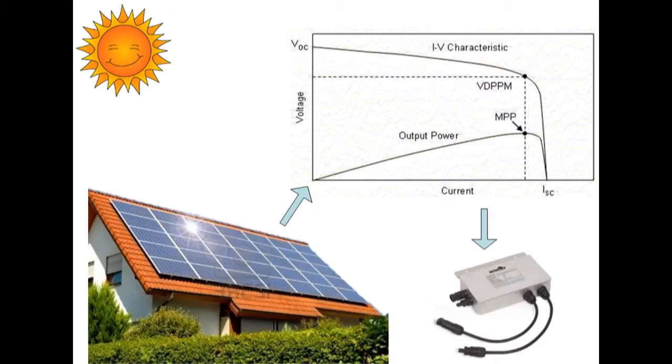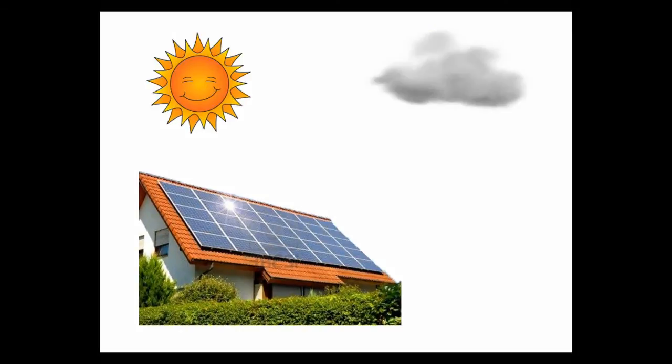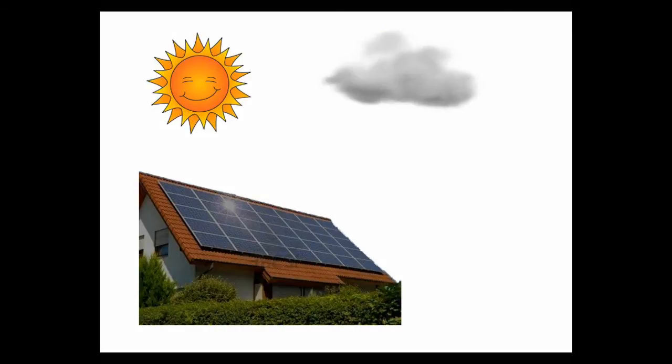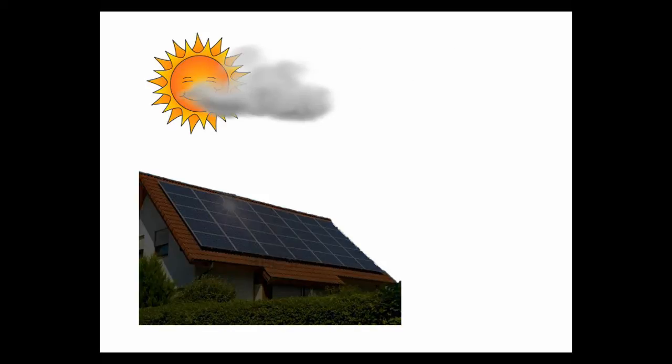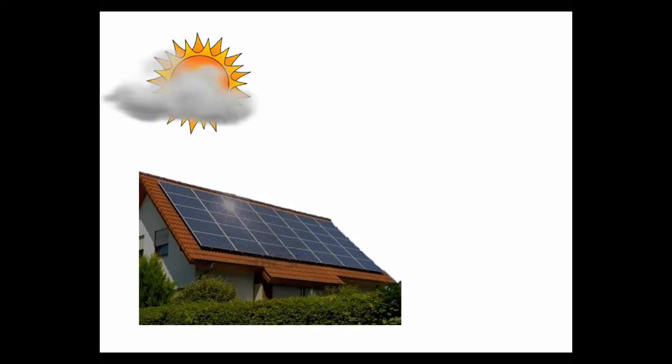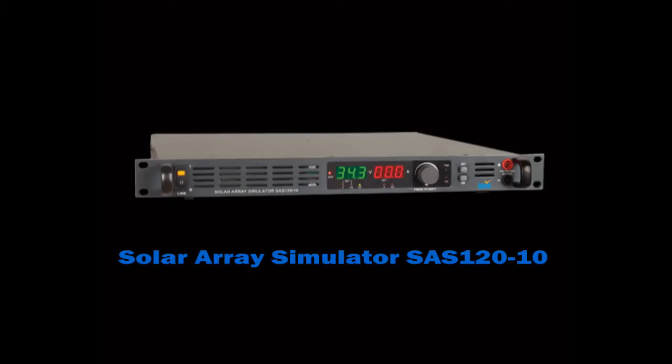PV arrays have non-linear voltage and current characteristics. In-house testing of PV application devices like microinverters, converters, and DC-DC optimizers require a power source with similar characteristics. Using solar arrays directly for testing is not possible because they are quite expensive and the output varies with varying temperature and irradiance throughout the day, and hence repeatability cannot be achieved.